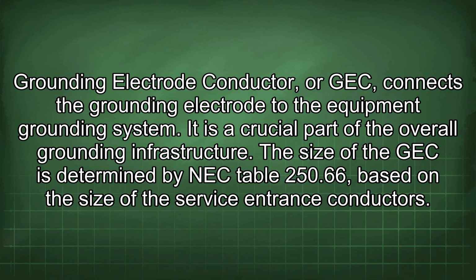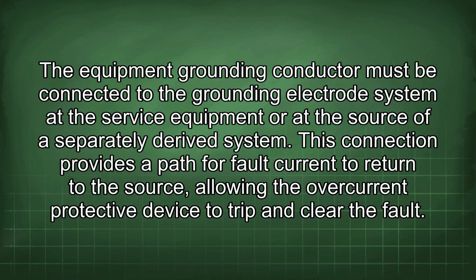The grounding electrode conductor, or GEC, connects the grounding electrode to the equipment grounding system. It is a crucial part of the overall grounding infrastructure. The size of the GEC is determined by NEC Table 250.66 based on the size of the service entrance conductors. The equipment grounding conductor must be connected to the grounding electrode system at the service equipment or at the source of a separately derived system. This connection provides a path for fault current to return to the source, allowing the overcurrent protective device to trip and clear the fault.